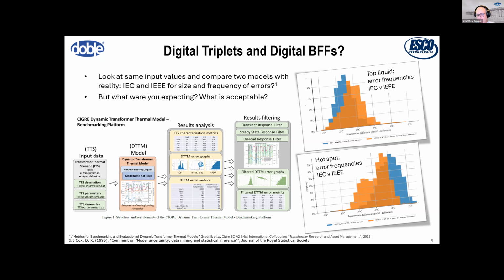In this case here, if you're looking at the hotspot temperature, IEEE is going to have it all spread out, and you see it's a little bit more compact than the IEC, around 0. So both these models, done by experts in the industry, still have differences you're trying to take into account for.